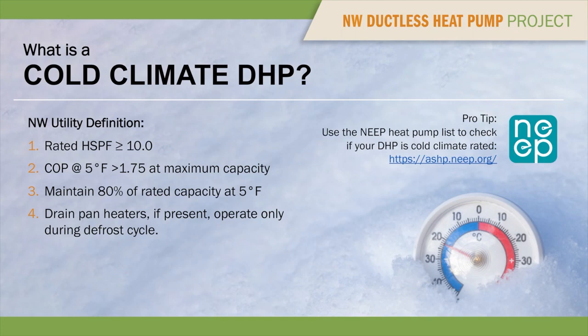For example, if a heat pump had a COP of 1, it means it would use 1 kilowatt of electricity to produce 3,412 BTUs of heat. For our cold climate heat pump definition, we want to see a COP of 1.75 at 5 degrees Fahrenheit. Since heat pumps are rated by AHRI at 47 degrees Fahrenheit, it became clear that we needed a standard that showed performance at 5 degrees Fahrenheit, which is a temperature that is more representative of a cold climate. We think a good cold climate heat pump, when operating at 5 degrees, should produce at least 80% of what it produced at 47 degrees.